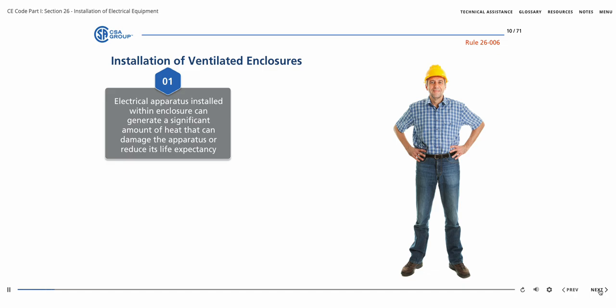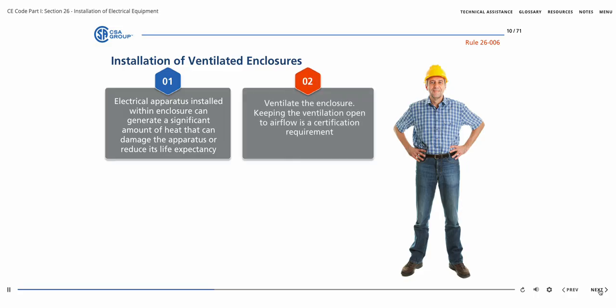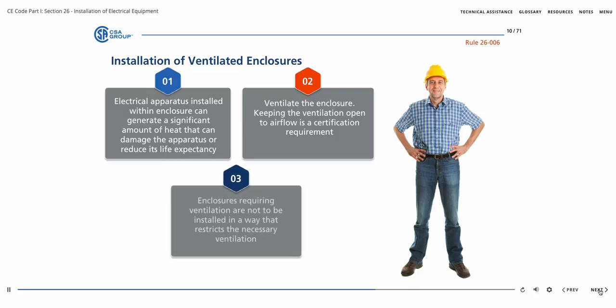When installed inside an enclosure, certain types of electrical apparatus can generate a significant amount of heat that can damage the apparatus or reduce its life expectancy. One way of keeping the heat buildup at a satisfactory level is to ventilate the enclosure. Keeping the ventilation open to airflow is also a certification requirement for these ventilated enclosures. Rule 26-006 requires that enclosures that are to be ventilated to avoid overheating are not to be installed in a way that restricts the necessary ventilation.